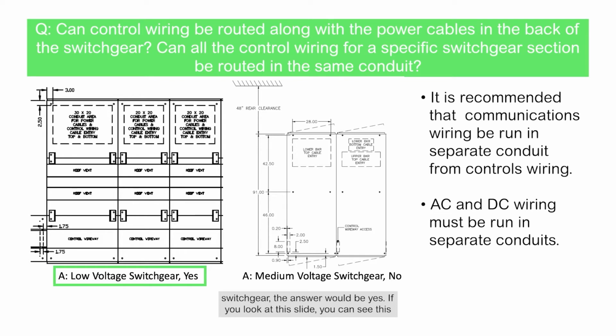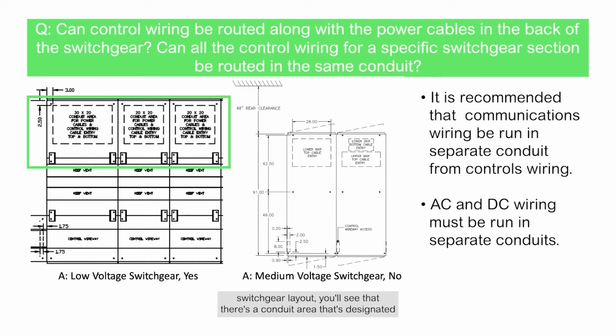If you look at this slide, you can see this is a top view of typical switchgear sections. On the top portion of that switchgear layout, you'll see there's a conduit area designated for the power cables as well as the control wiring brought into that section for the various controls for the generators and transfer of the ATS as they're connected to the system.